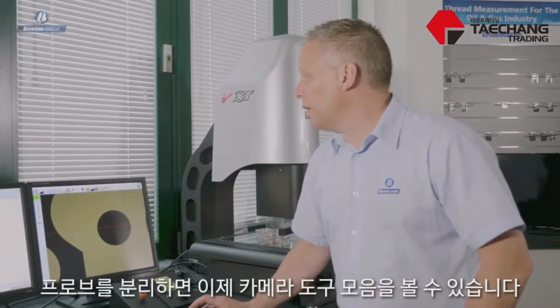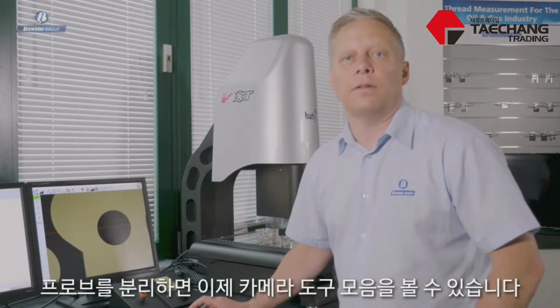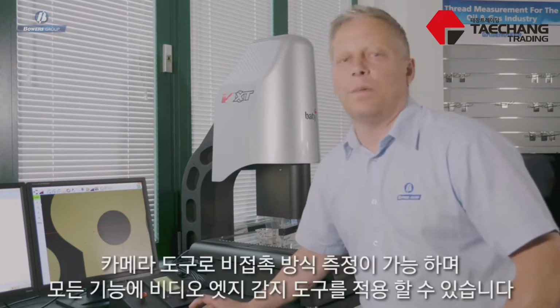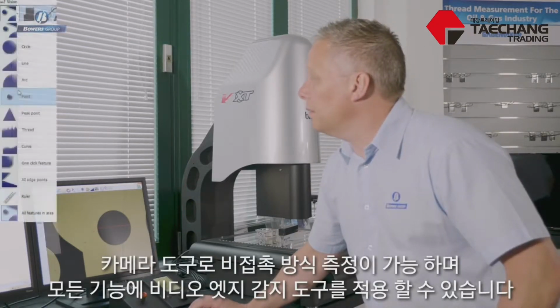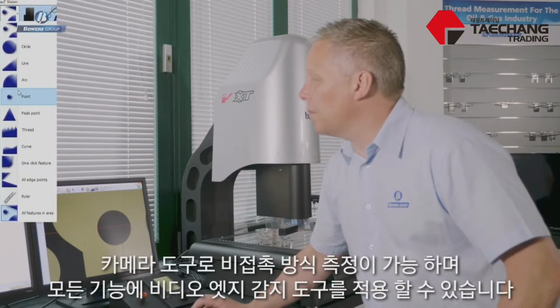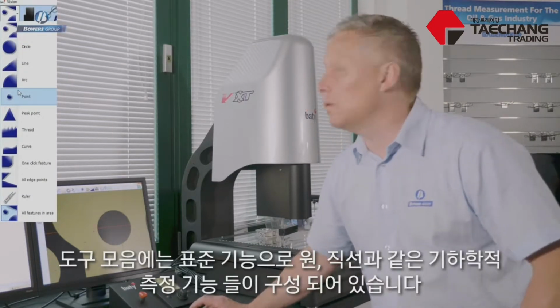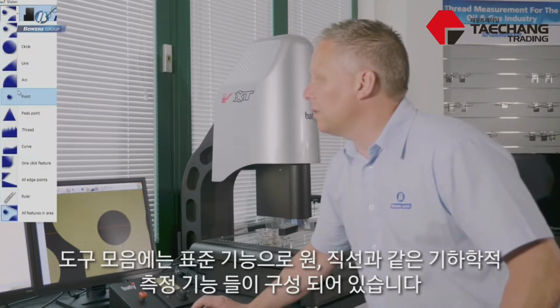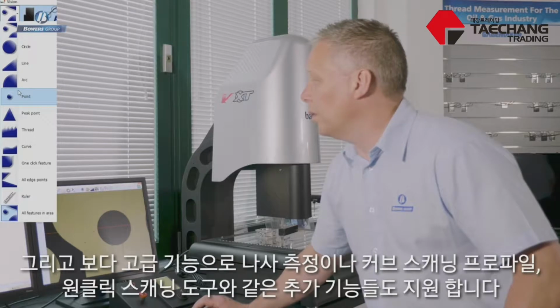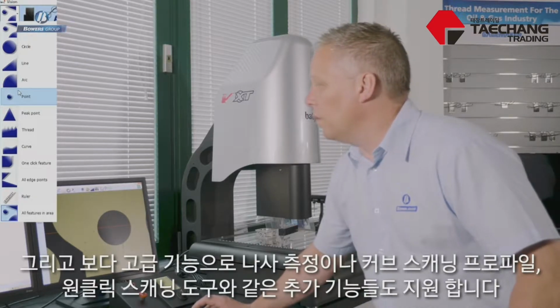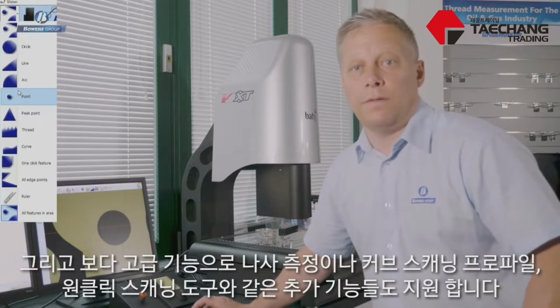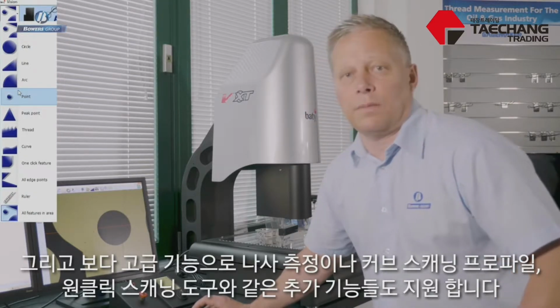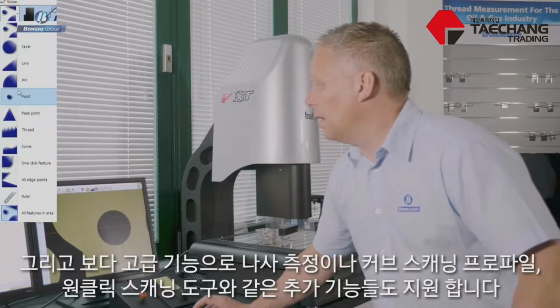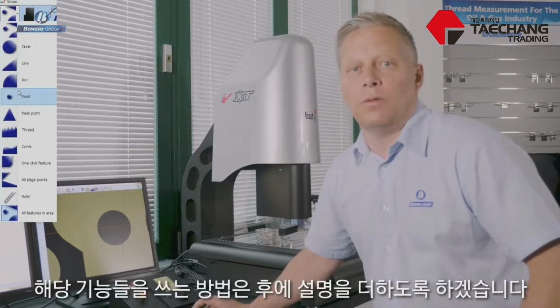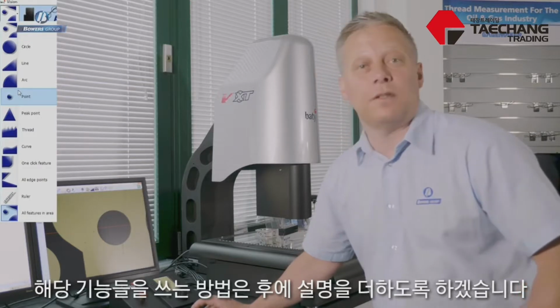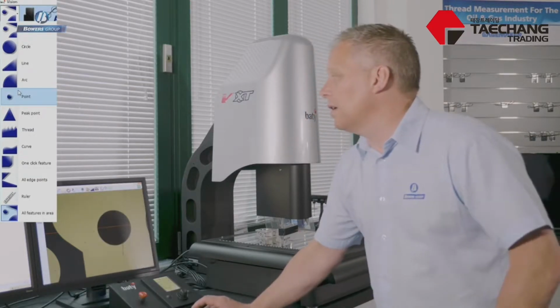So, having put the probe away, we can now look at some of the camera tools that we've got available for measuring features by non-contact. Here you can see a list of tools that I have available to me. These are all video edge detection tools, ranging from the standard geometric features like circle, line, arc, point, and so on. And we've got some more specific functions to Fusion, like thread tools, curve scanning, profile scanning tools, one-click feature, and a great new tool, which is all features in an area. So we'll come on to those later.